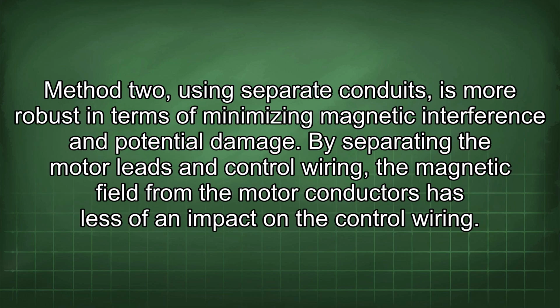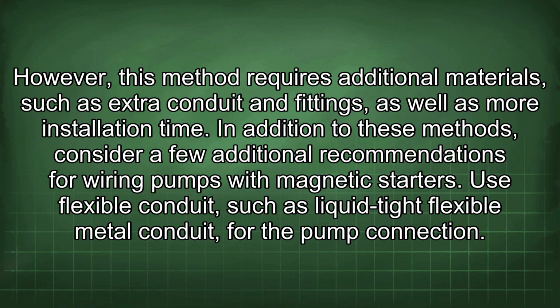Method 2, using separate conduits, is more robust in terms of minimizing magnetic interference and potential damage. By separating the motor leads and control wiring, the magnetic field from the motor conductors has less of an impact on the control wiring. However, this method requires additional materials, such as extra conduit and fittings, as well as more installation time. In addition to these methods, consider a few additional recommendations for wiring pumps with magnetic starters.